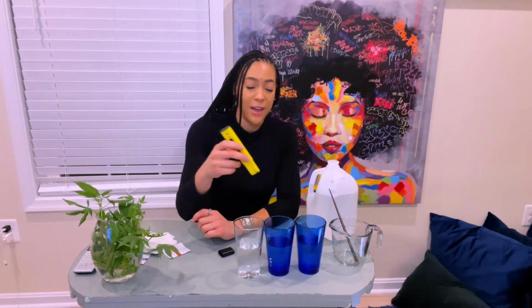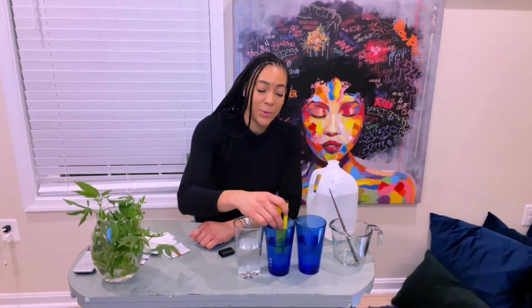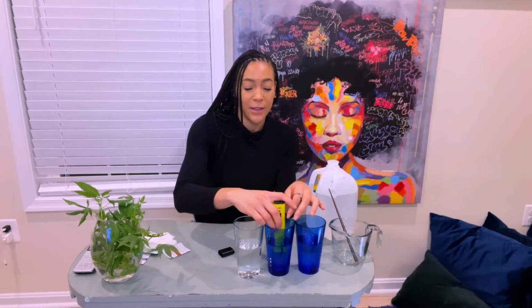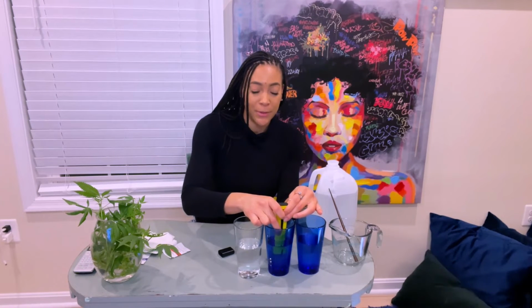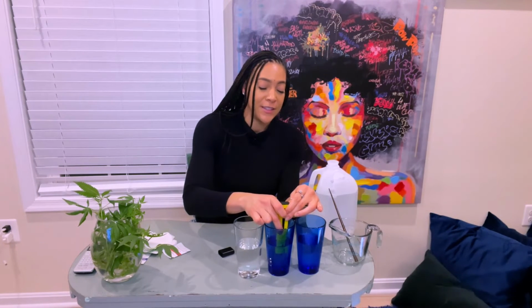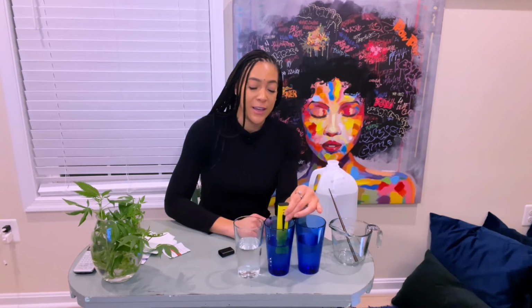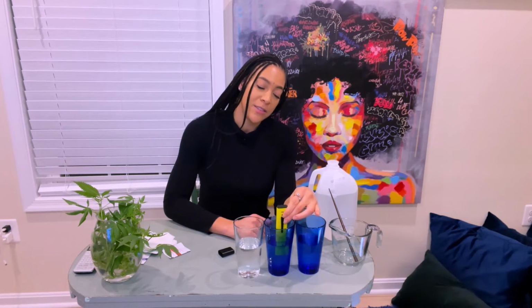Okay, so we're back and we have our solutions that are diluted into the 250 milliliters of water. So this is our 4.0 solution and this is our 6.86, and this is just our plain distilled water. So the first thing I want to do is turn on our pH meter, and I'm going to put this into the 6.86 solution, let it settle for a second, and then I'm going to press the calibration button and hold it 1, 2, 3, 4, 5 for 5 seconds. It's flashing, and then it gives me an end, and it gives me a 6.86 reading, which is perfect.